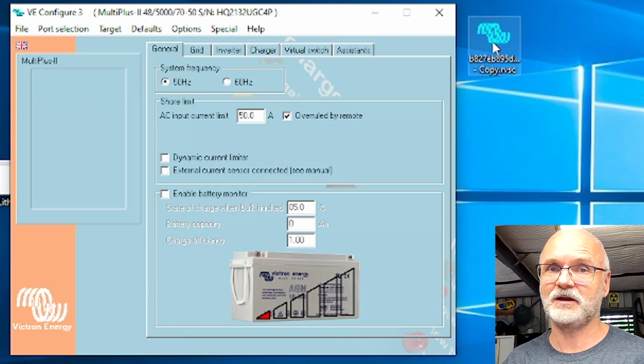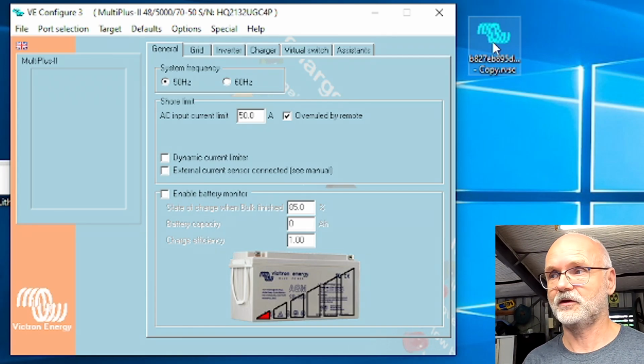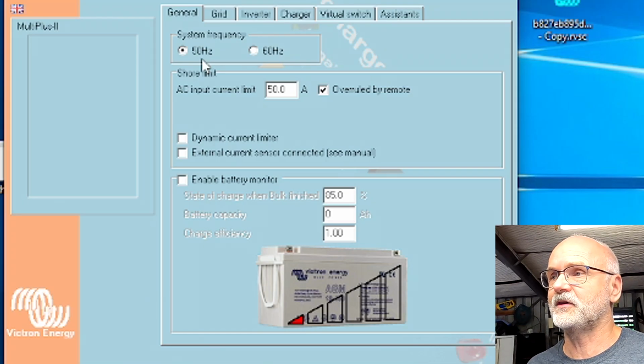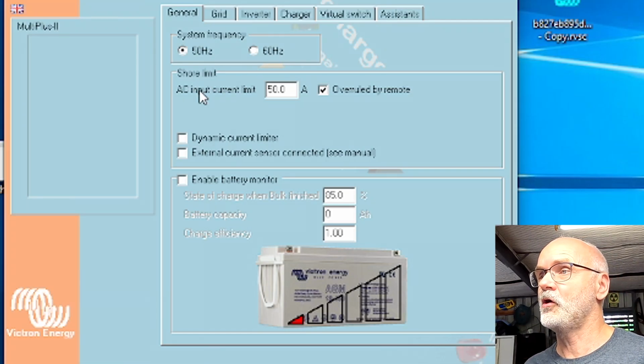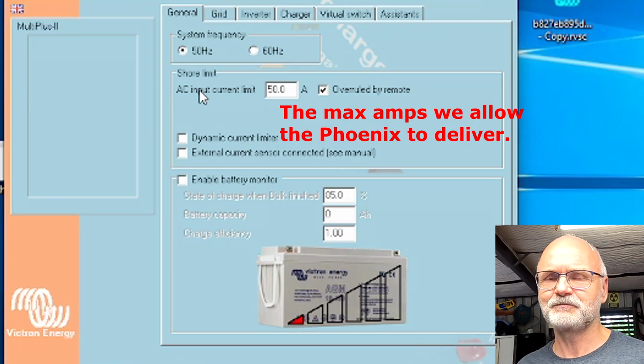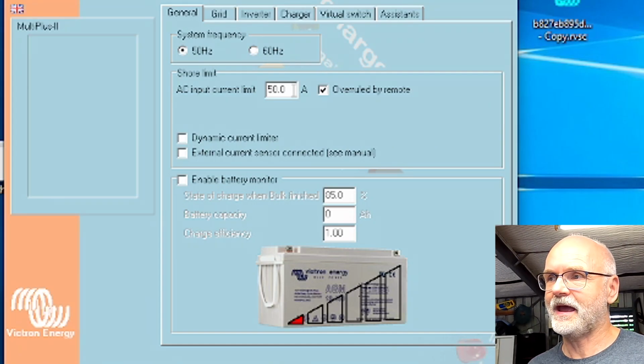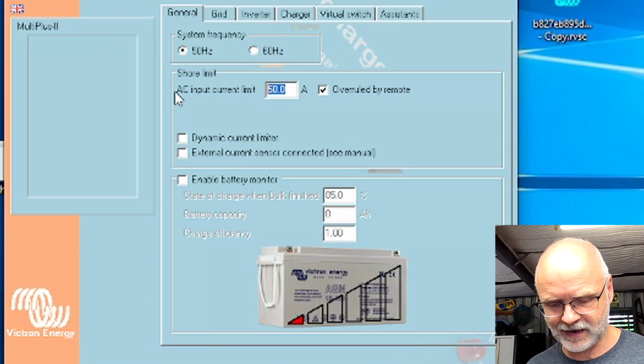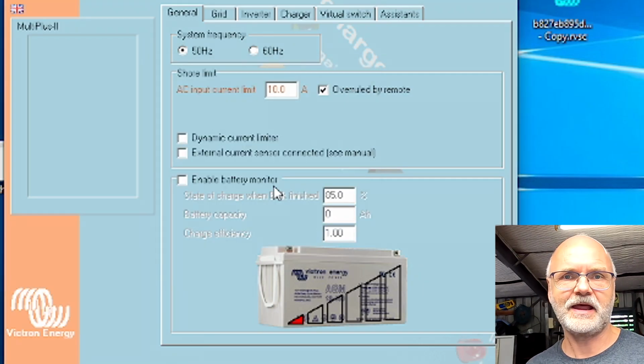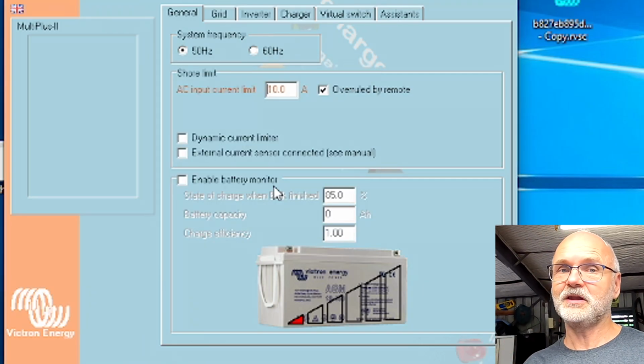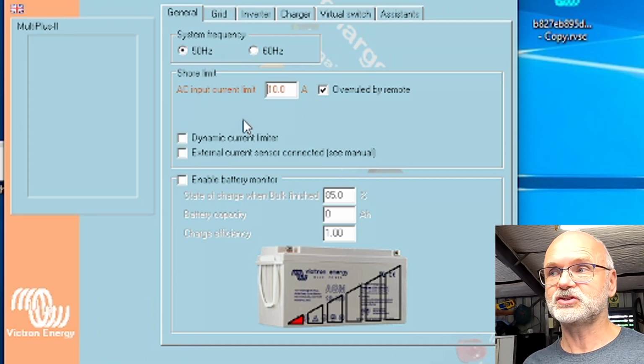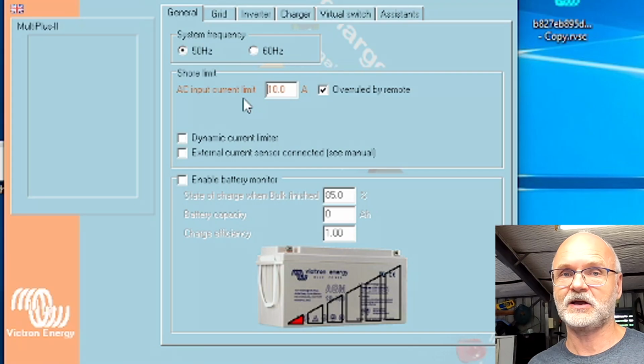This is as the Multiplus was delivered. In the general tab, we can find the system frequency, 50 to 60 Hertz, and also the shore limit. This is exactly the threshold we can set up in the Multiplus for the Phoenix inverter. See, it sits by default on 50 amps, which is the maximum that the internal transfer switches can do. We can potentially set this up to 10 amps, meaning it will allow the Phoenix to work up until 10 amps, and then additional power will come from the Multiplus. Whenever you make a change in VE Configure, it changes the color of that item, so you know which parameters you have actually changed already.